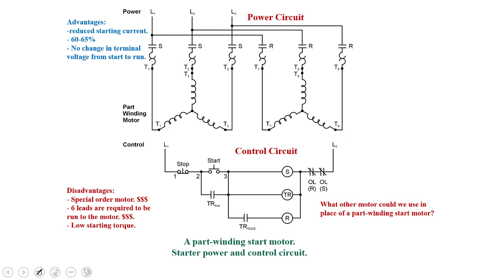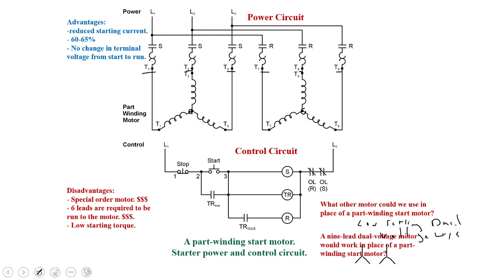So on that note, what other motor could we use in place of a part winding starter if need be? Well, in the first objective here, you read about your 9-lead motors. And if we use the low voltage setting on a dual voltage Y motor, we could do that, because basically what are we doing with it? We're doing parallel Y, right? In the low voltage setting on a dual voltage motor for Y. So if you cross-reference this back to objective 1, you're going to see 1, 2, and 3, and then you'd have to make the star, and then 7, 8, and 9 on the run winding, and that star will already be made for you right there. So a 9-lead Y motor would work for this condition here, right?